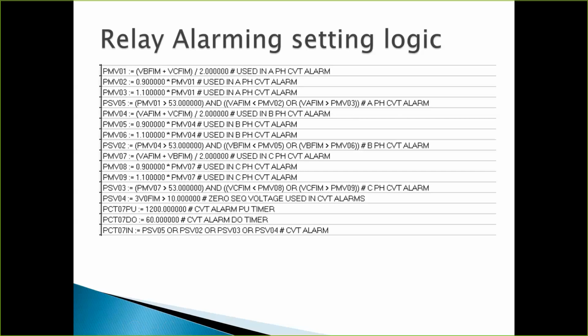These are the actual settings, but we'll look at a picture and make a little more sense in just a minute. So I've got the average of B phase and C phase. I compare it to A phase. Is it 10% above or below? Is it greater than 53 volts? If it is, I alarm. If not, I move on. Again, a loss of potential is different than an alarm.